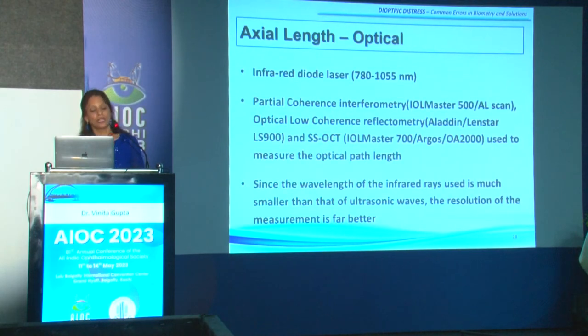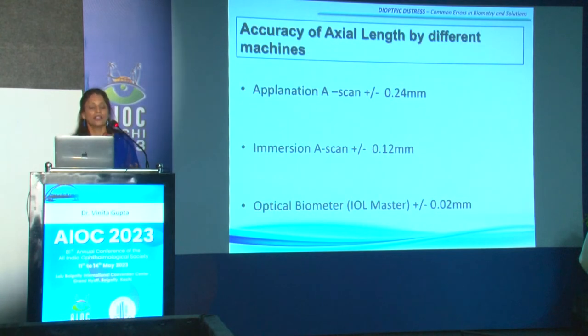Now, next is your optical biometers, which use infrared diode lasers and are based on various principles. We have PCI based, OLCR based, and swept source OCT based optical biometer machines available to us. The basic thing in these machines is the resolution is far better because of the wavelength we are using, the infrared rays. If you look at the accuracy, with the A scan it is somewhere between 0.12 and 0.24, which is markedly improved with an optical biometer.